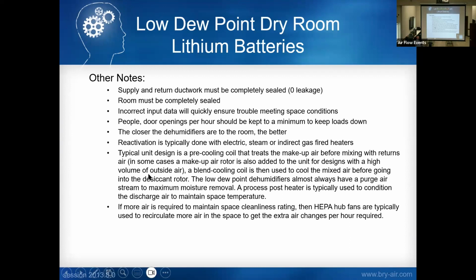Typically, these units have purge to get down to that. We've got a delivery area in that -80, -90 dew point, so we use a purge. All the air comes in through a common outside air opening. That air gets pre-cooled, mixes with return air, which gets cooled again. Then we pull off some of that air through what we call purge, which is another sector in the desiccant rotor. It goes through that sector and then feeds into the reactivation. So the reactivation air is dry going into the rotor, just like the process air. And that's what allows us to achieve that -80 dew point that we need.